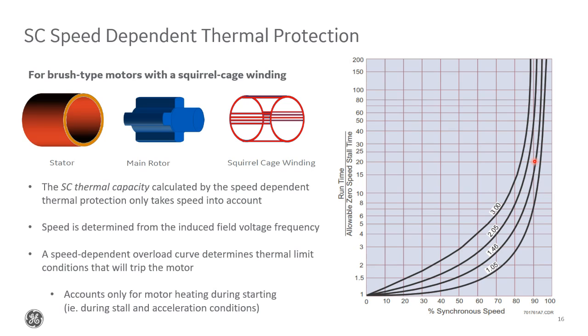In terms of protection elements, one of the key new features we added is the squirrel cage speed-dependent thermal model. The idea with this is that, like I mentioned earlier, most synchronous motors have a squirrel cage winding that facilitates the motor starting in induction mode while it comes up to speed. Since this cage isn't designed to be used during running operation, it's usually made of a lighter material and it could be vulnerable to overheating. So if the motor stalls during acceleration or if the motor runs out of sync for too long with no DC supply, we could run the risk of damaging that cage winding. So the intent with the squirrel cage speed dependent thermal protection is to look at the motor speed during acceleration and estimate the cage's thermal state based on how long it's been operating at that speed.